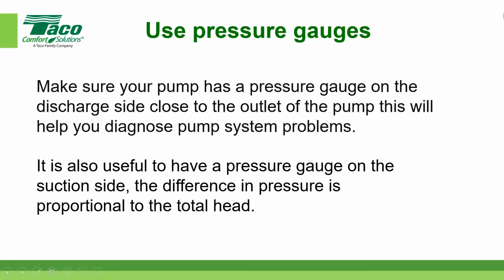Yeah, and actually, this came up only a week or so ago, Brett. And it turned out that there was nothing wrong with the pump. They had too high a pressure drop on the suction piping, and that created the negative pressure at the inlet of the pump. As soon as they put the compound gauge on, they realized that the pump was in fact doing the pressure differential, but the pressure was so low on the suction side of the pump, it was starting to cause the pump to cavitate. So it was an important little tidbit.